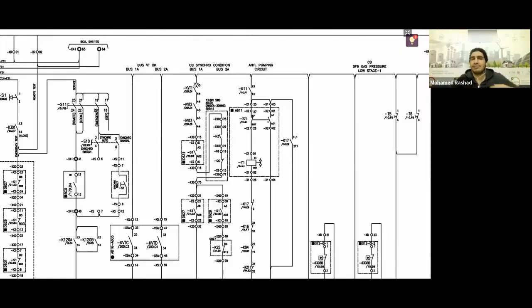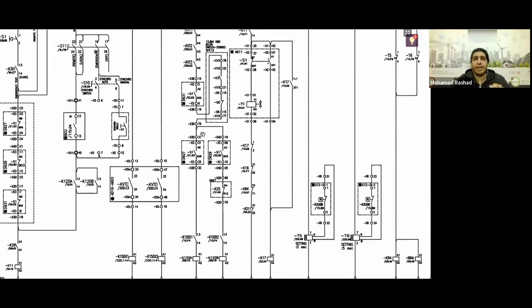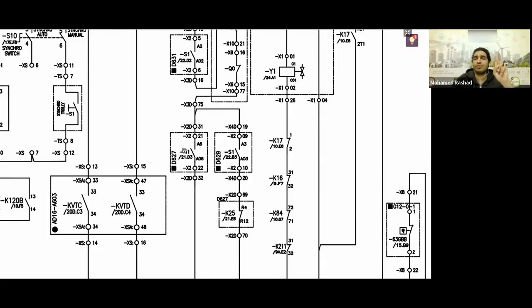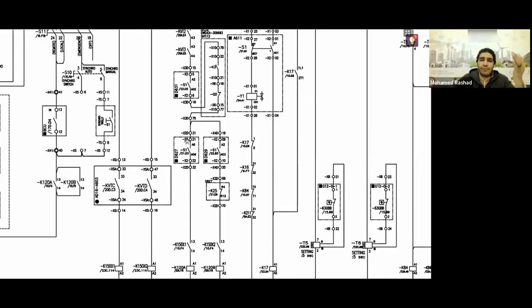Yes, this is the idea you have. What is engineer Fadi saying here? He is telling you that you just told me that you checked the data of your teleprotection and confirmed that your line disconnector is closed and that the downstream circuit breaker is open. Then you came here and told me there's something between the two. Either the disconnector D627 of the upper bus is closed or the disconnector of the lower bus is closed. Exactly. So if you look, if the disconnector of the upper bus is closed, one of the conditions you would check is that the VT of the upper bus is intact. What does intact mean? It means that the auxiliary is working as a result of the VT isolator and the VT MCB, and the second VT MCB in the LCC and in the box, both are closed. So you were checking these conditions for K120 to operate.